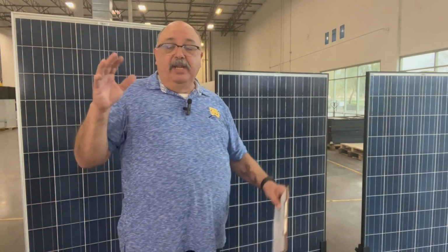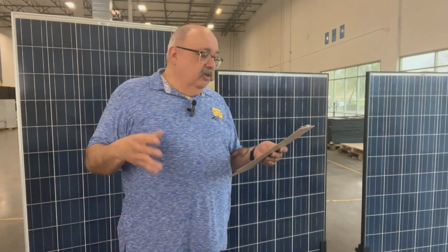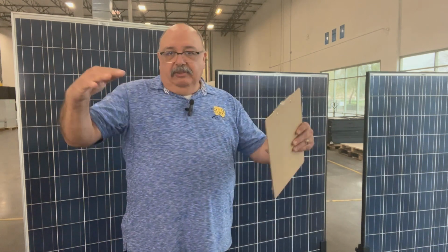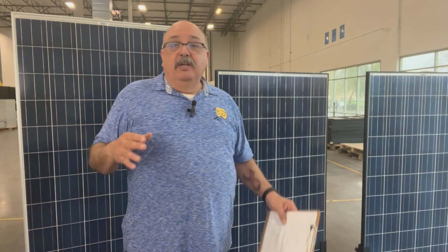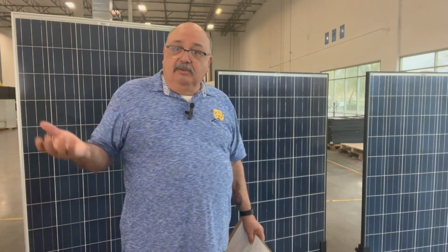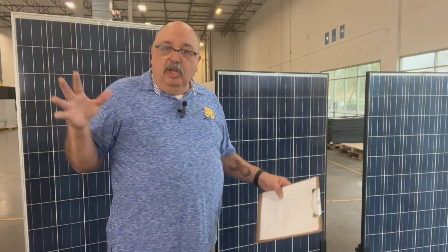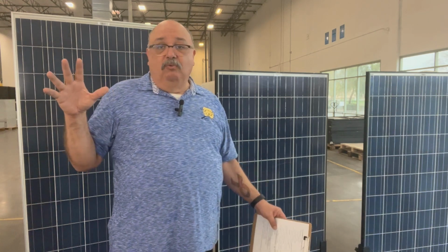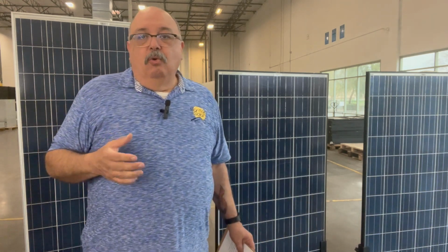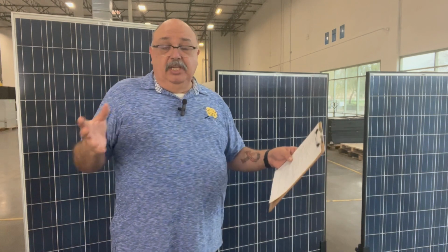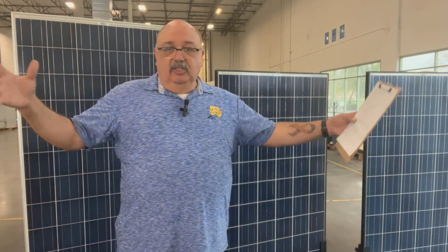Now, say you're going to use something a little bit bigger, like maybe a 410 watt panel. You're only going to need about 12 of those panels. Now, they are a bit wider and bigger, but you're going to use fewer of them. And if you configure them as 4 panels in 3 rows, you're looking at about 254 square feet based on the dimensions. So you can get a smaller space with the same wattage for 5 kilowatts. Or you can use a lot of panels to achieve 5 kilowatts, but they're going to be spread out more. So that's something you might want to keep in mind.